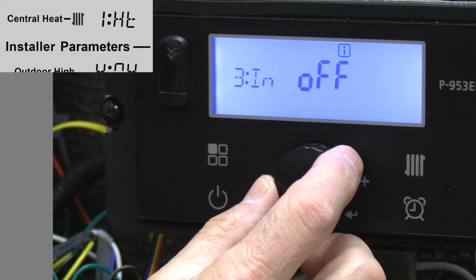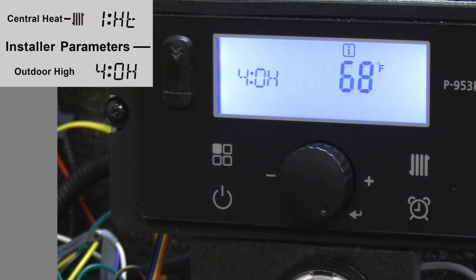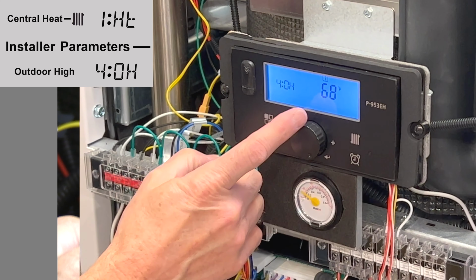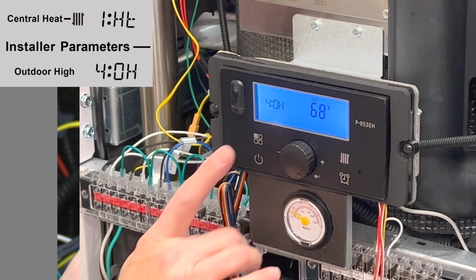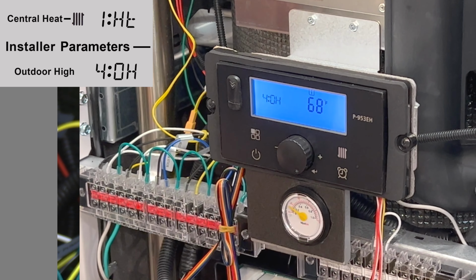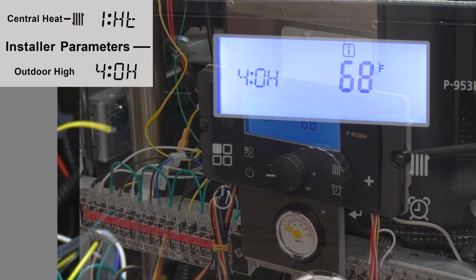Next, we want to scroll to parameter 4. That's our outdoor high for our reset curve. And we have some defaulted values in here that are very conservative. So you may want to adjust those to really take advantage of condensing and high efficiency. So in my example, I'm going to take my outdoor high at 68 degrees. This is not warm weather shutdown. This is the outdoor high. And I'm going to drop that value.